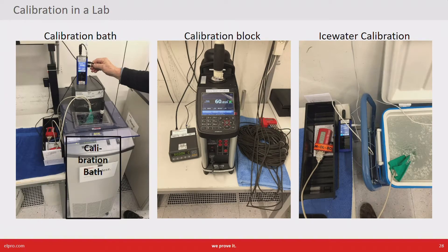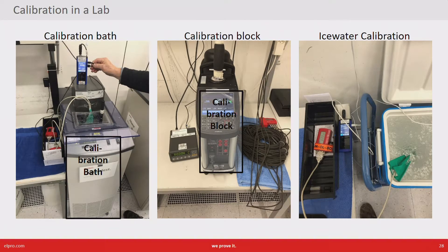The second example is a block calibrator. A block calibrator has the advantage that you can travel with it, so you can go to a customer on site. It can calibrate temperatures from minus 200 to plus 400 degrees. However, it has the disadvantage that the space for calibration is very small, so all you can do is calibrate external sensors — you cannot dip an entire device inside.